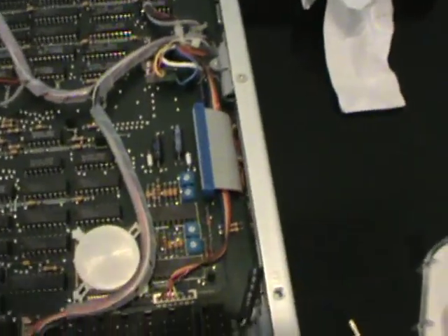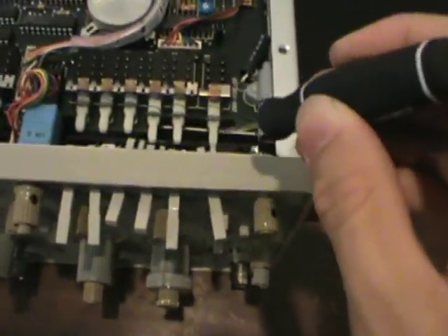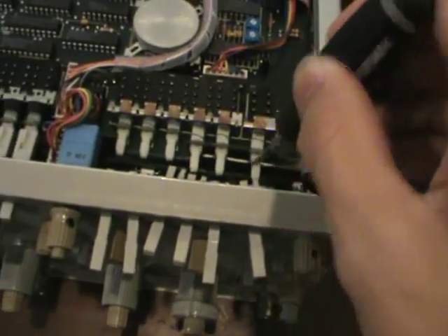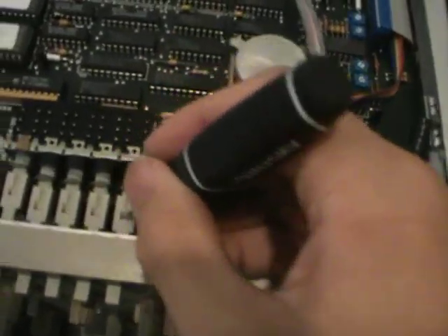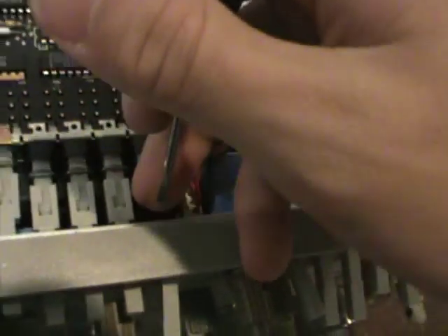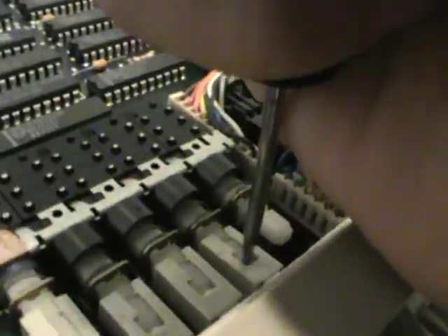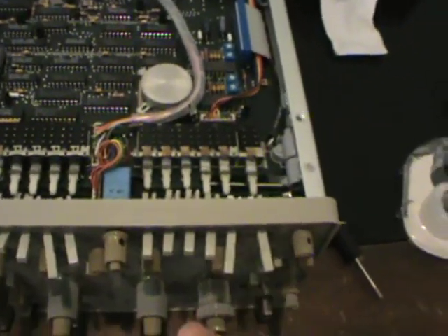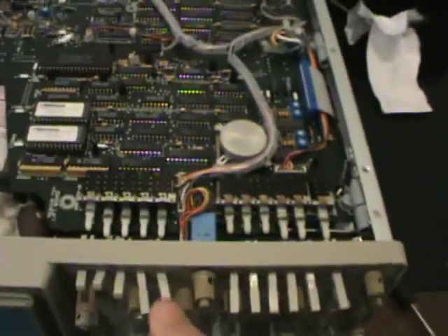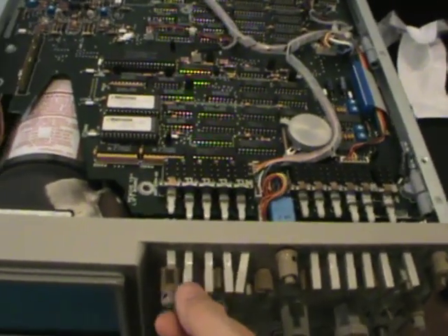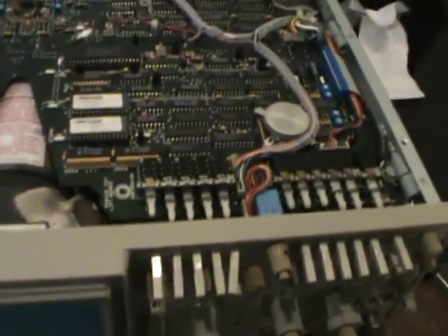To remove this acquisition board, what you'll have to do is press down on the switch and pull back with a flathead screwdriver like this. So look. Observe. Down. And then back. Gotta put a little bit of force into it. There we go. Again. Down. And back. Here. Push down. And then back. Down. Back. And then down. And then back. This hopefully does not damage it but it is the way that we are told to do it in the service manual for this oscilloscope. So I don't think it should be causing any harm.